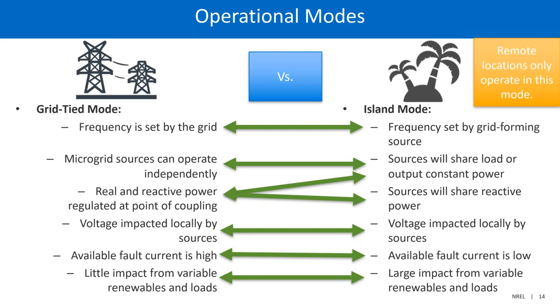In island mode, the frequency is determined by your sources, so the sources you put in the grid are the ones forming the voltage and frequency. The nice thing about the utility is that if you're not producing enough power, they provide that extra power. When you're islanded, all the power for your grid, both real and reactive, has to be produced by the sources on the grid, and there's nowhere else for it to come from.